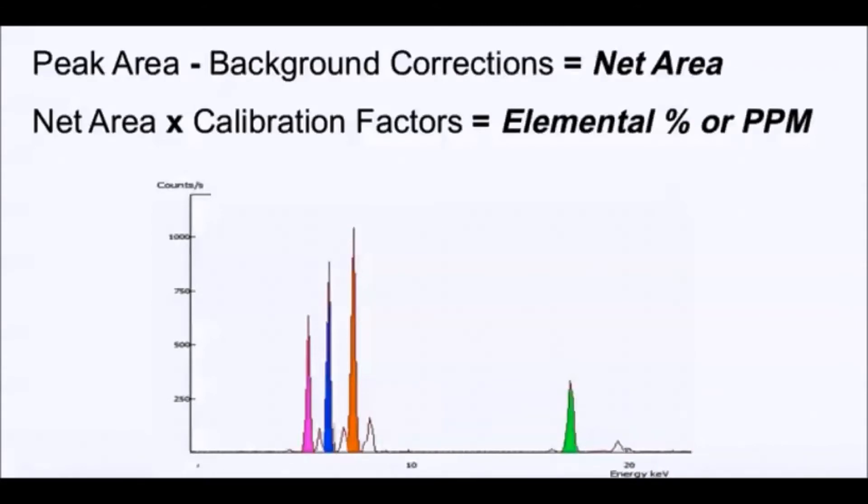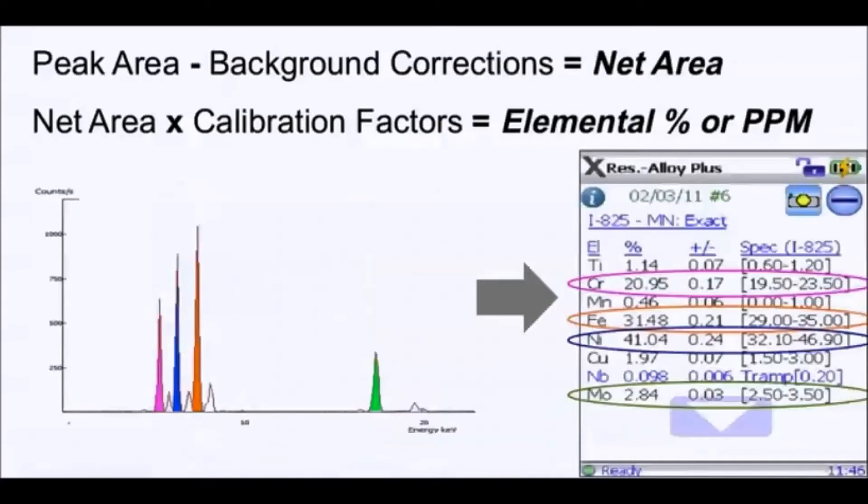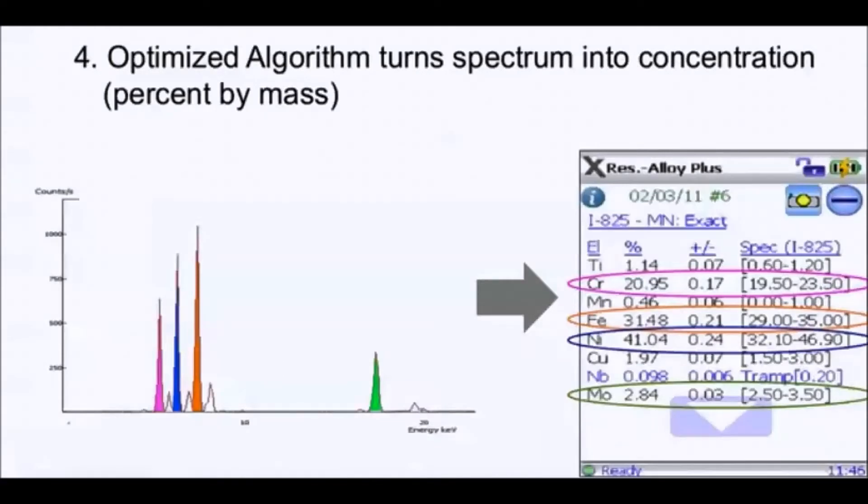This process, as far as the user is concerned, is really real-time. The test starts and the answer is directly displayed. The emitted energy in real-time is turned into an elemental analysis, as you can see on the right of the slide. The algorithms are different from application to application, but all of them turn in a quantitative result.